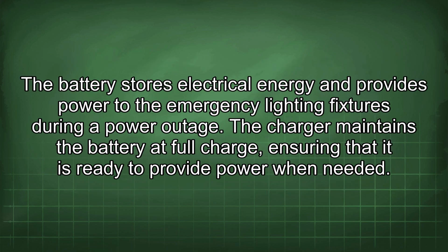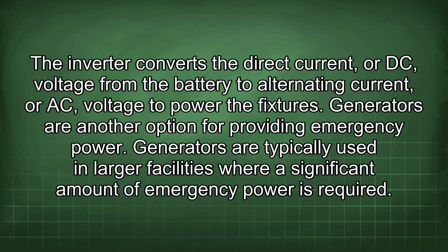The battery stores electrical energy and provides power to the emergency lighting fixtures during a power outage. The charger maintains the battery at full charge, ensuring that it is ready to provide power when needed. The inverter converts the direct current, or DC voltage, from the battery to alternating current, or AC voltage, to power the fixtures. Generators are another option for providing emergency power.